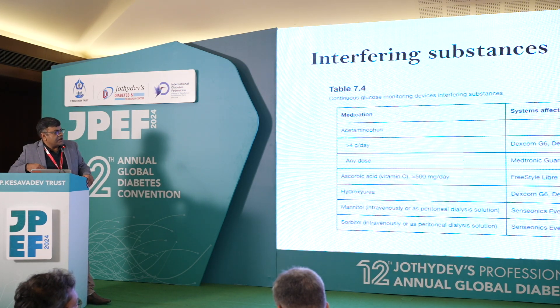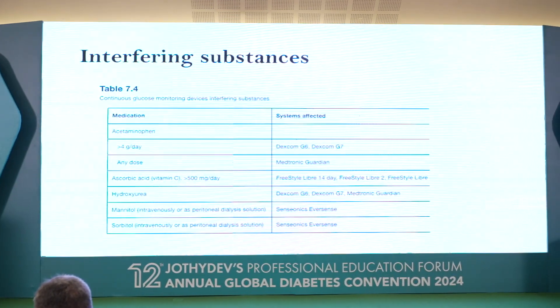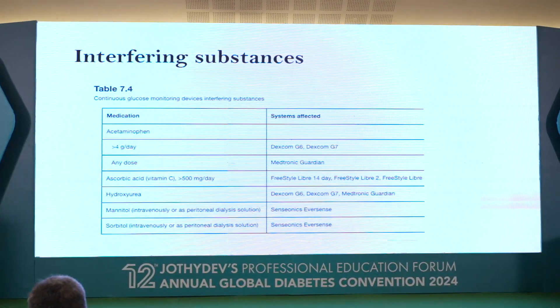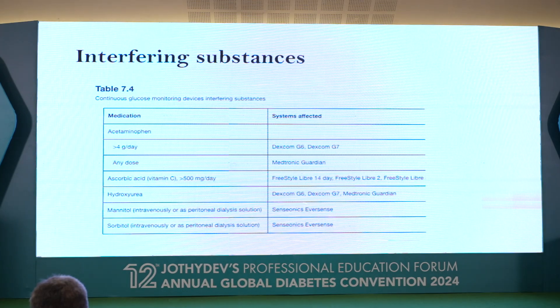Regarding substances that can interfere with CGM readings: acetaminophen at higher doses can interfere with Dexcom G6 and G7, and at any dose can interfere with Medtronic Guardian devices. Vitamin C at levels more than 500 mg per day can interfere with Libre devices, though as heard from a colleague, up to 1 gram per day may be acceptable — more than 1 gram might interfere. Hydroxyurea can interfere with all these devices. Intravenous use of mannitol or sorbitol can have some interference with Eversense devices, which are implantable CGM devices.